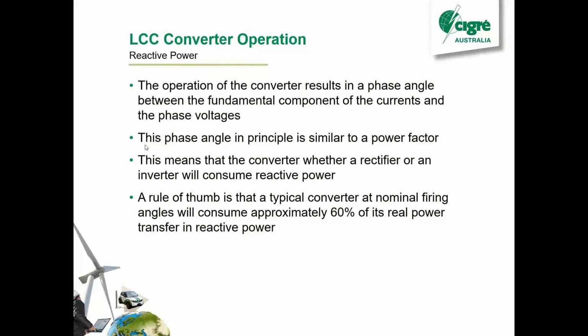Okay, it's worth mentioning reactive power with LCCs. So you can see with that alpha, we're waiting as the voltage comes up, we're waiting until we fire our thyristor. So inherently, we're drawing current out of phase with voltage. And that means reactive power, right? If you draw current in phase with voltage, that's all real power. But because we're delaying it, we are going to have some reactive power. So it's kind of similar to power factor. And it means whether you're rectifying or an inverter, you will consume reactive power from the AC network.